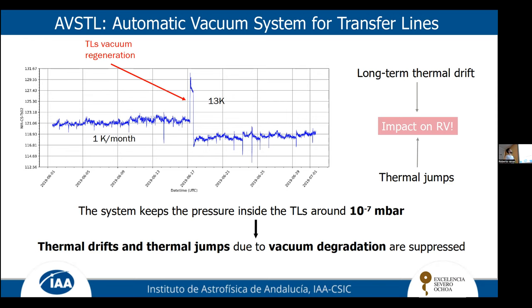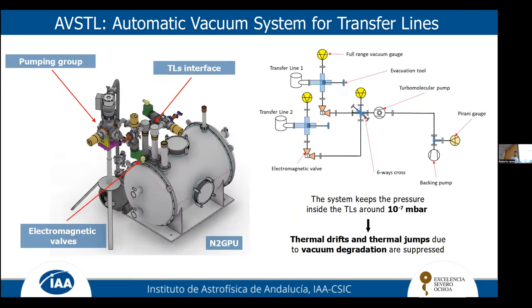So here about 13K that we want to avoid, because, as I told you, the main goal is to have a long and short term stability of the instrument. So basically, to avoid this long-term thermal drift and the thermal jumps, we installed this system, the automatic vacuum system, that keeps the pressure very stable around 10 to the minus 7 millibars.